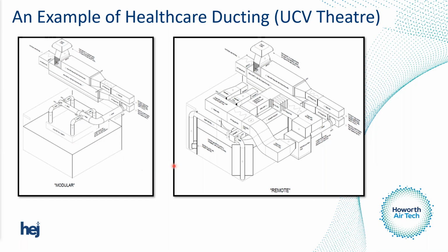So in the UK, we have 2 options. We have a modular or remote type UCV. 98% of the canopies that Howorth sell are a modular type unit. And then these sort of canopies you may see knocking about the industry would be called a flush type canopy. You'd see it flush within the ceiling. Now, the benefit of having this type of system is you can take a pitot traverse here to get the total volume to the operating theatre.